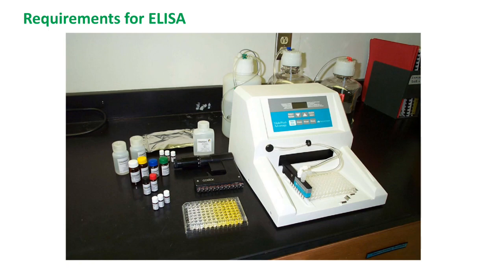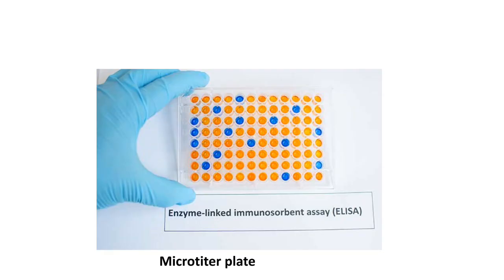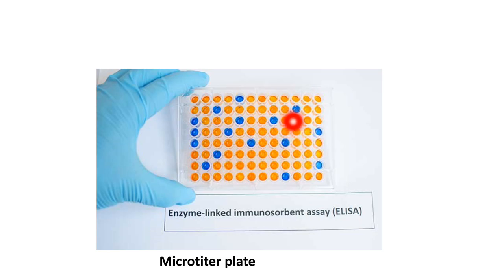Here you can see the ELISA washer and reader instruments, as well as micropipettes, microtiter plates, and reagents including enzyme conjugates and wash buffers. The microtiter plate contains 96 wells. Initially we add positive and negative controls and standards, and based on the concentration of the analyte, the color is developed and quantified by spectrophotometer.